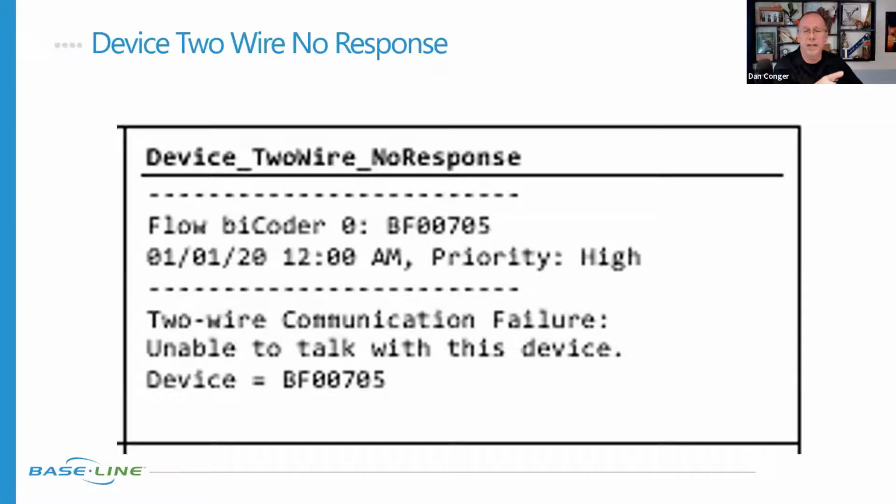And I like that idea. If you saw a grouping of these, it's just not a one-off. If it's a grouping of these, what are the odds that 10 devices are bad? Right. It's very rare, or even a lightning strike, because oftentimes the lightning event doesn't result in this type of failure. It would result in a short oftentimes.